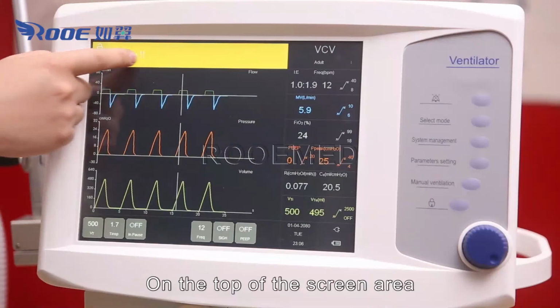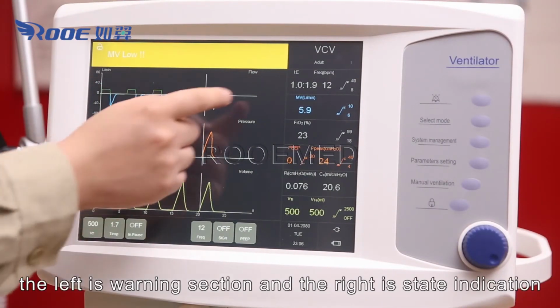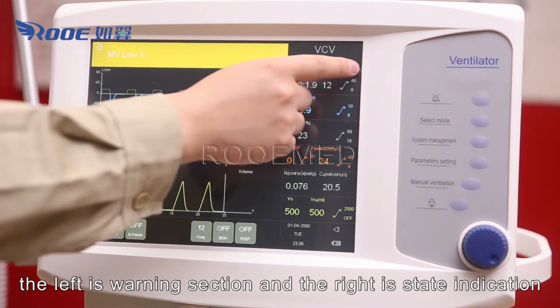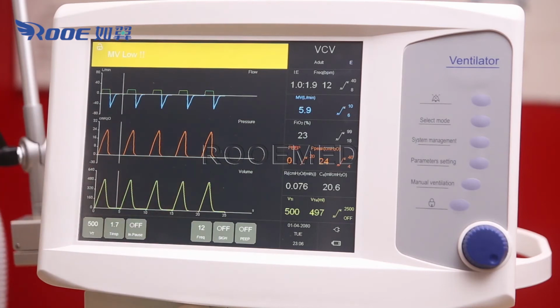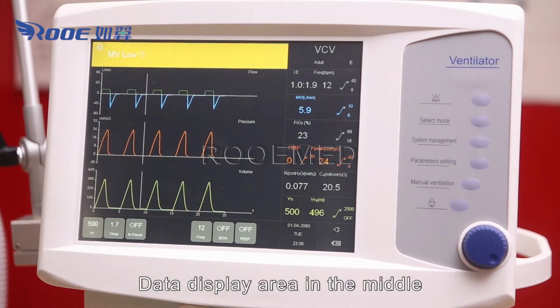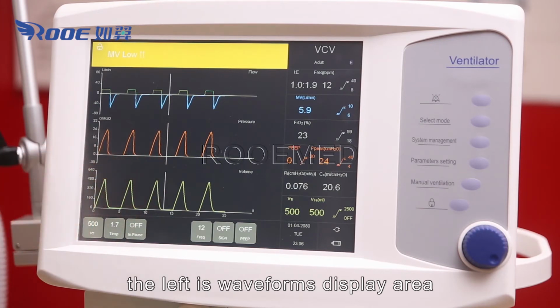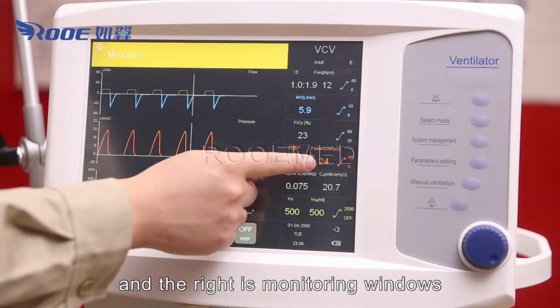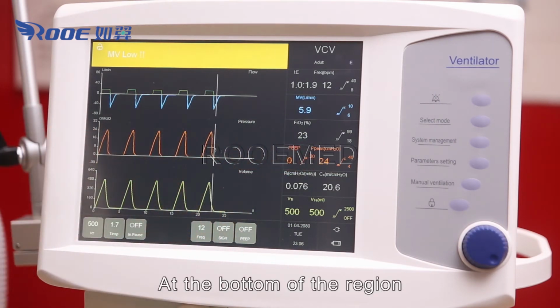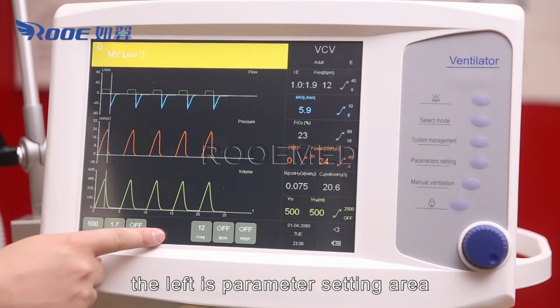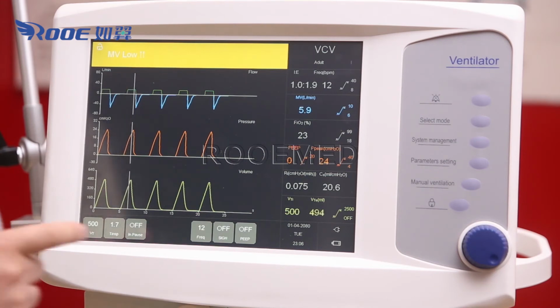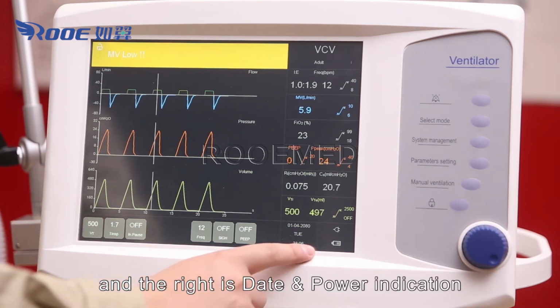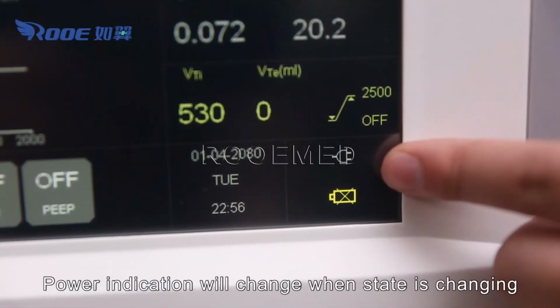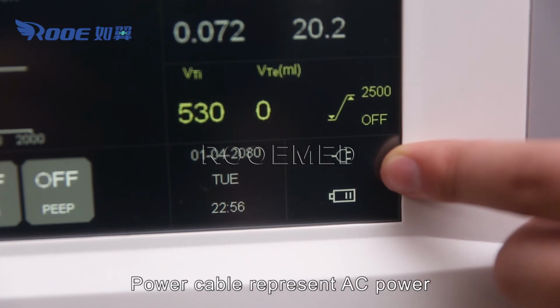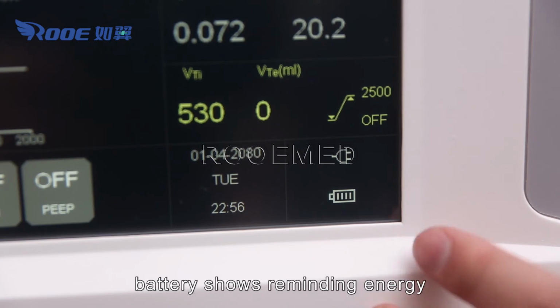Composition of the screen area. On the top of the screen area, the left is the warning section and the right is the state indication. Data display area in the middle. The left is the waveforms display area, and the right is the monitoring window. At the bottom of the region, the left is the parameter setting area, and the right is the date and power indication. Power indication will change when the state is changing. Power cable represents AC power. Battery shows remaining energy.